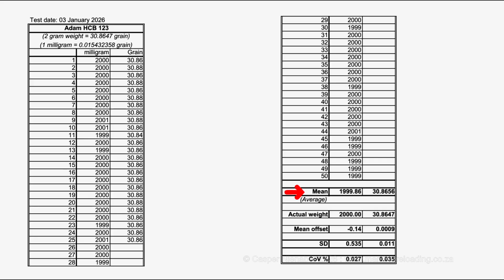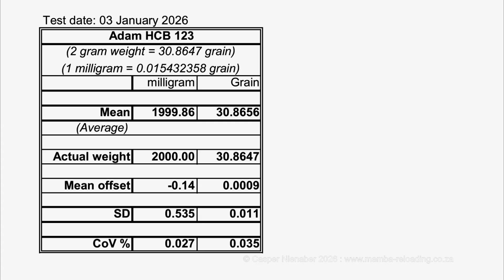I calculated the mean, average, standard deviation, SD, and coefficient of variation, COV. Let's zoom in on the results. The mean weight of 1,999.86 milligrams is only 0.14 milligram below the true weight of 2,000 milligrams.